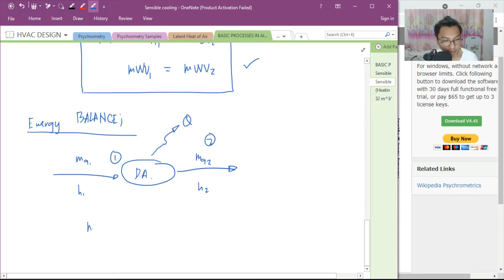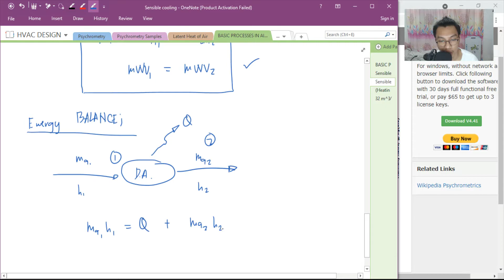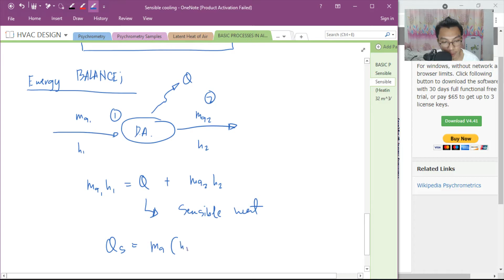So, ano ibig sabihin natin dyan? Yung mass ni dry air 1 multiplied to H1 equal to Q plus mass ni air at 2 times H2. Simplifying, yung Q natin dito is sensible heat. So, QS is equal to MA (H1 minus H2). That is the formula. And also, pwede naman natin gawin ganito. Equal din yan sa MA CP ng air multiplied to temperature dry bulb 1 minus temperature dry bulb 2.